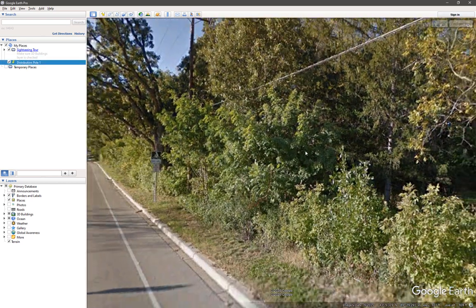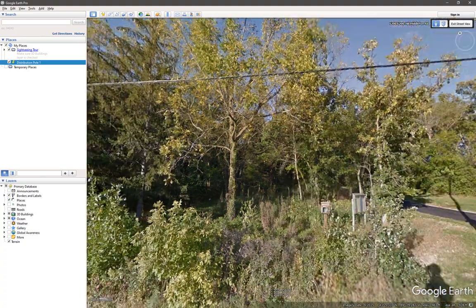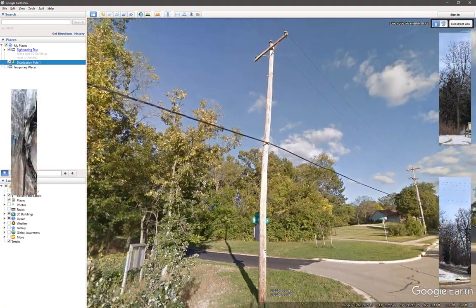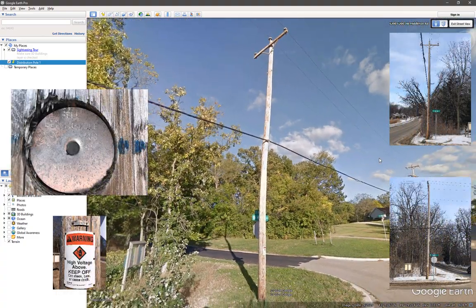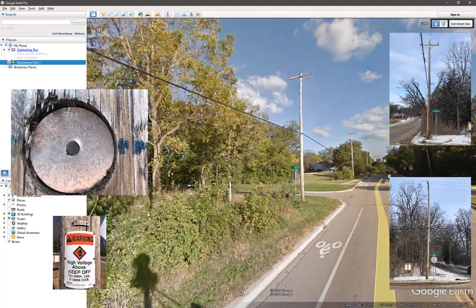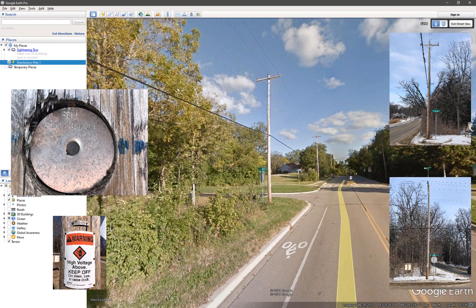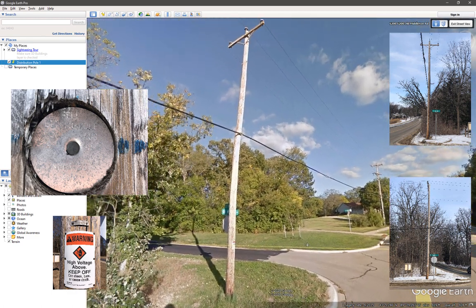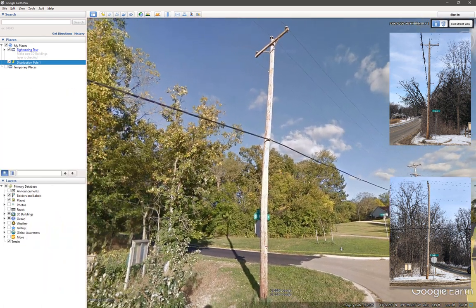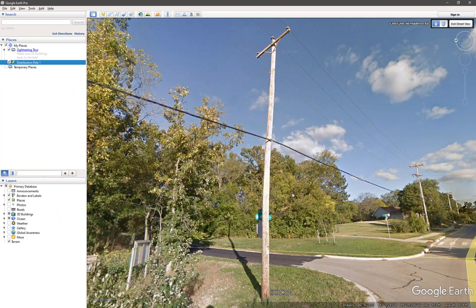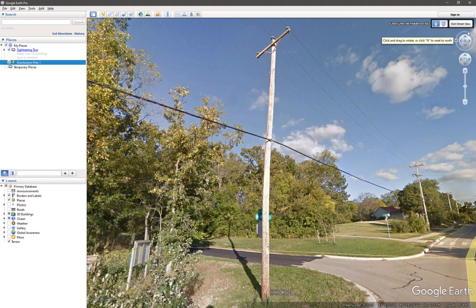From a quick site visit to this structure, we were able to take pictures of the structure and spans, as well as the birthmark on the pole so that we know it's a 45-foot Class 4 Douglas fir pole. The pictures show us that it's a typical three-phase distribution structure with a drop-neutral and a communication wire attachment further down.